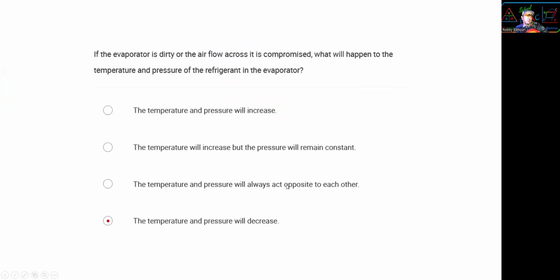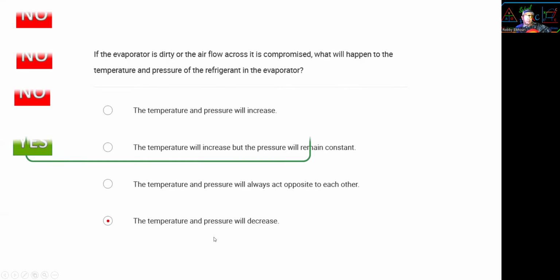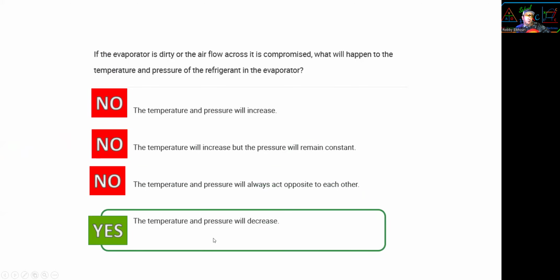Right, now, if the evaporator is dirty or the airflow across it is bad, what will happen? Temperature and pressure will increase, go up. Temperature will increase and pressure remains constant. No, that doesn't sound right, they go hand in hand. Temperature and pressure will act opposite of each other. No. Temperature and pressure will decrease. Correct. There we go. All right, next.